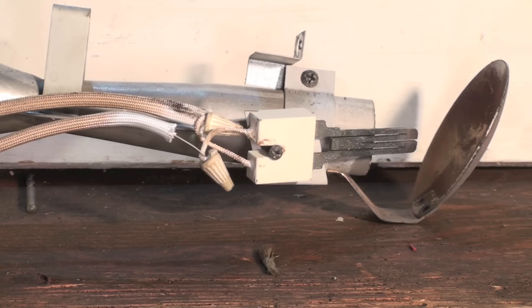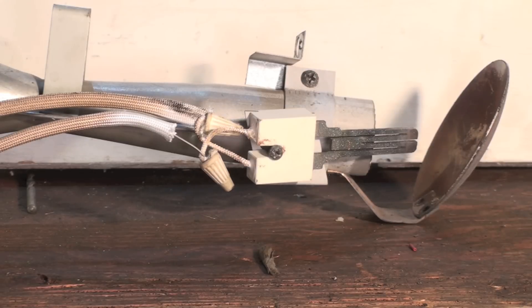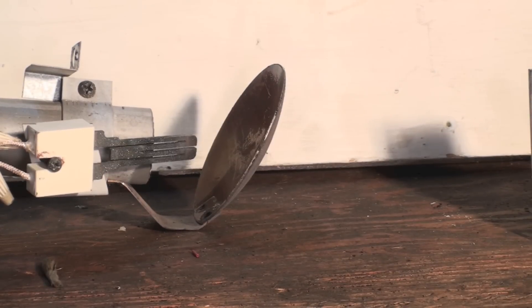In a lot of cases these things have problems using just the hot surface igniter for the flame sensing, so a lot of these were changed out. What happens with this, the fire just comes out here and it's got kind of a little target there and that spreads the fire out and of course it goes up.